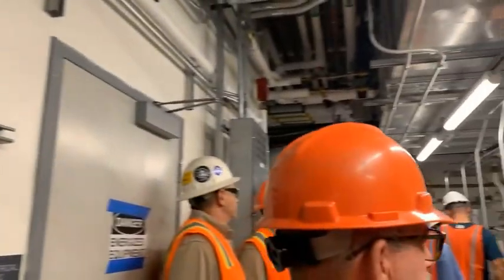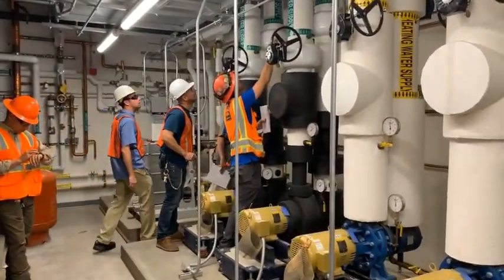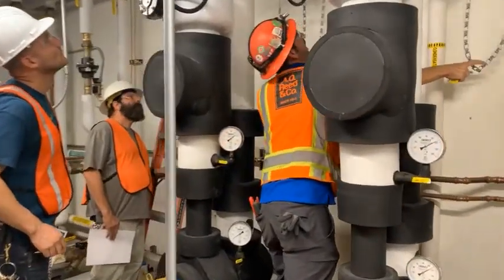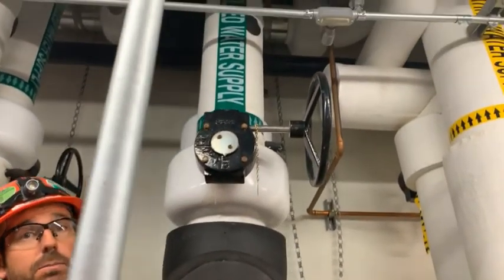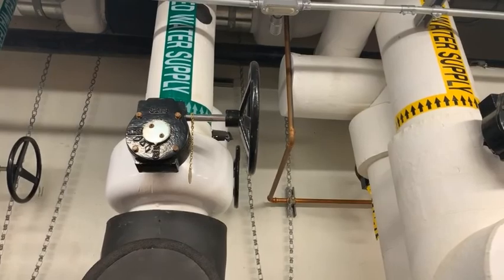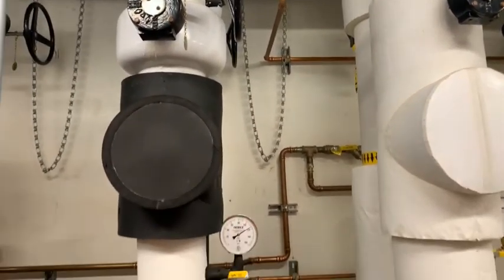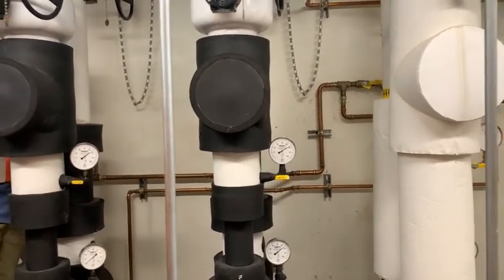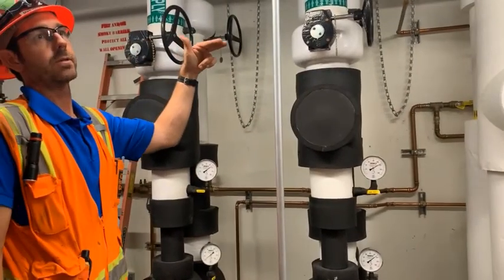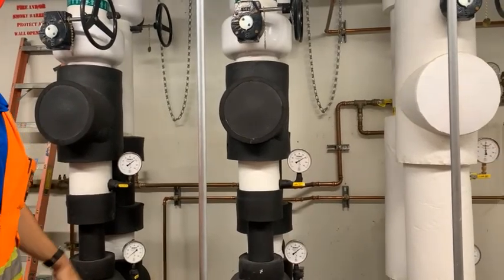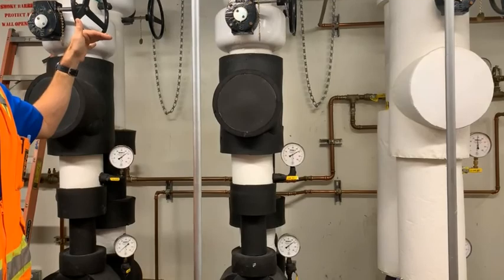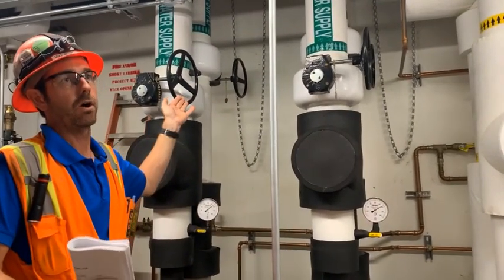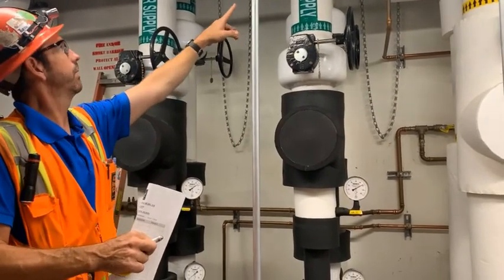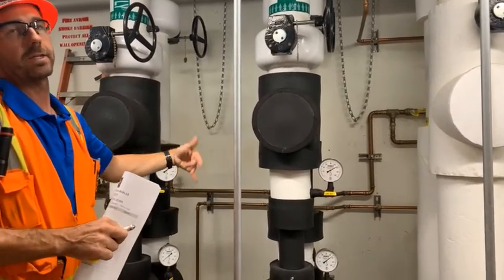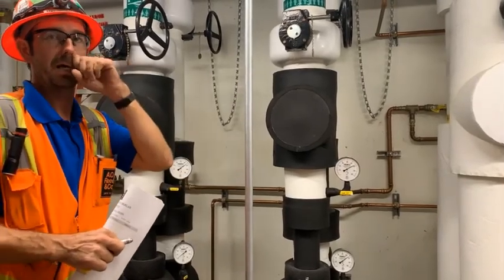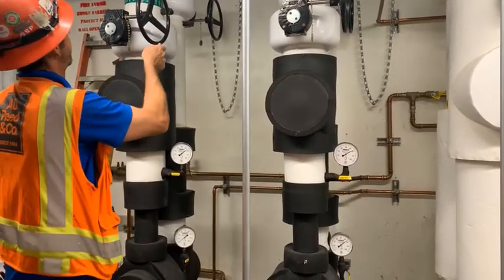Right up here, it's a big black insulated box. It's not a box, it's a foam insulation. Right up here. So it's this chain wheel right here and this chain wheel right here, 2 shutoff valves. The check valve is in between it. So we can flow chilled water around the pumps. Okay? So back to the VFD, it's important that those VFDs stay in auto at all times. Is that a normally open? Normally open valve, yes. No actuator on it? No actuator, it's just a check valve, so water can't go backwards through it. So it's only going to go through it. It's open all the time. Yep. That way, in low demands, maybe in like the winter, there's IDF rooms out here that are chilled water cooled. So in that low demand, we can run the water through that bypass. We don't want to run water through a pump unless the pump's running, okay? Because it can start spinning the pump and you can backfeed the VFD with electricity, okay? So that's the point of that valve up here.